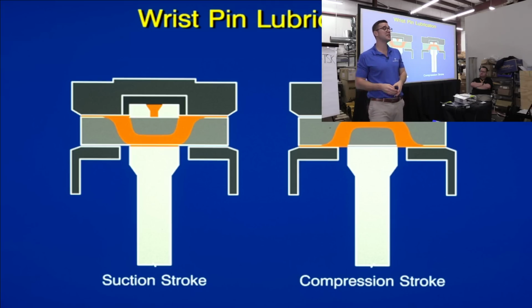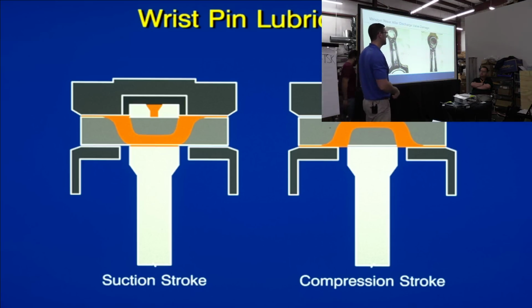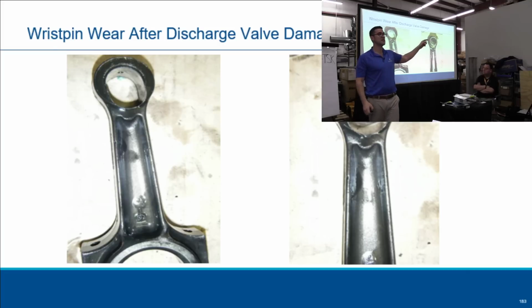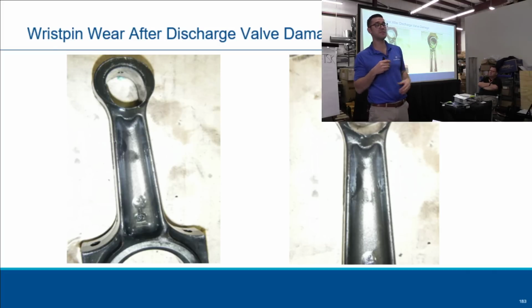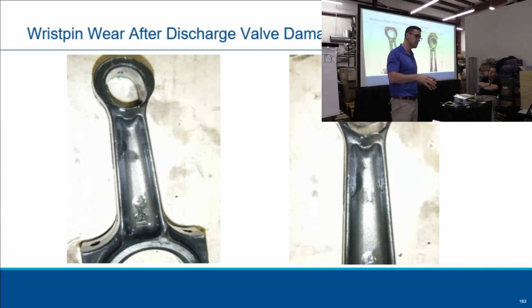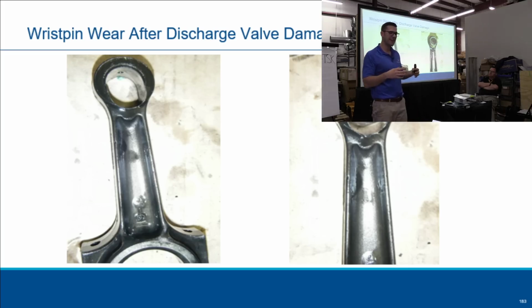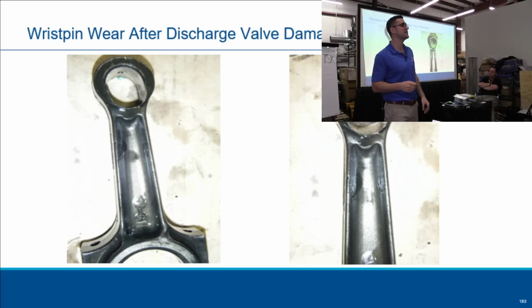How many people have heard of a semi-hermetic knocking? Knock, knock, knock, knock. You have? Well, this is what happened. That wrist pin not getting the oil, fighting that discharge. So you come in as a mechanic and you find this compressor, pull off the head, and it kind of sounded a little funny. You pull the head off, look inside, and it's a broken discharge valve. Awesome, we can just replace the valve plate.